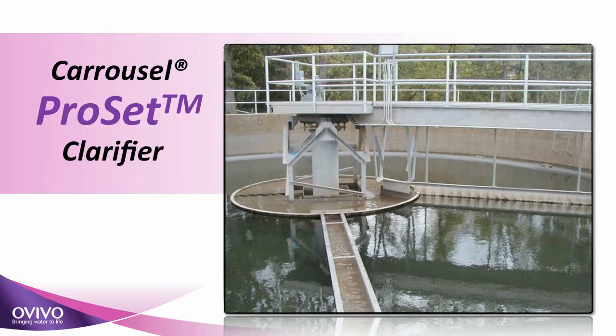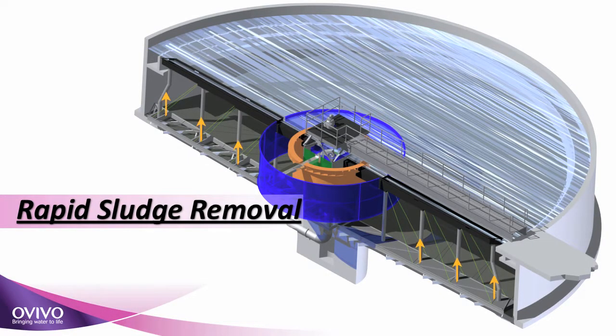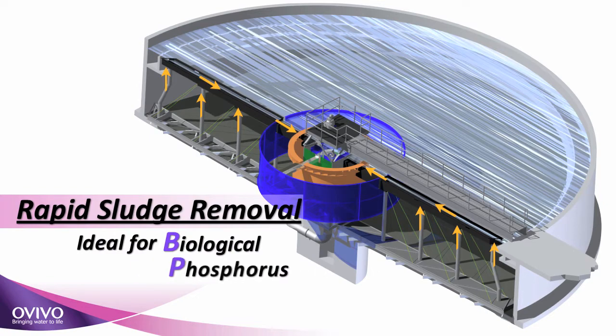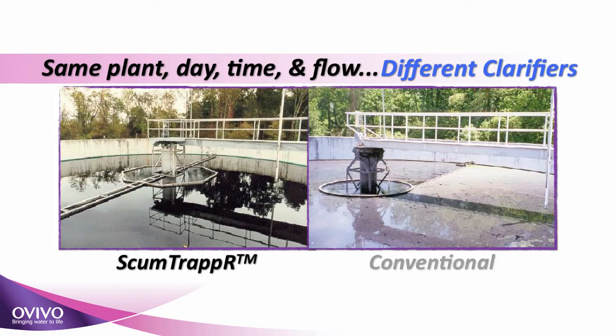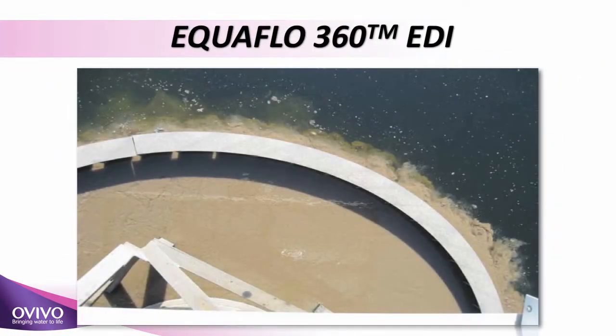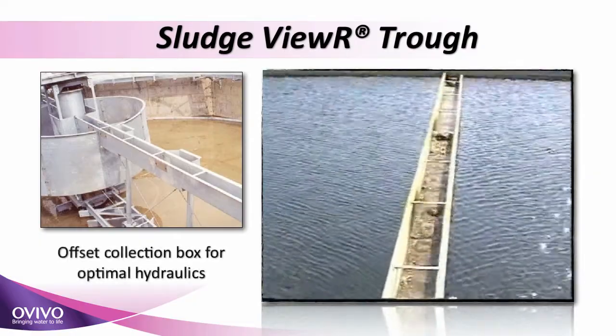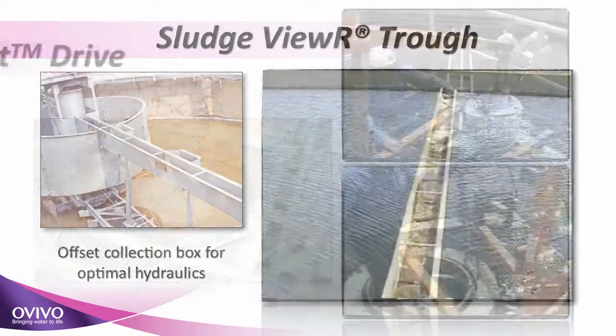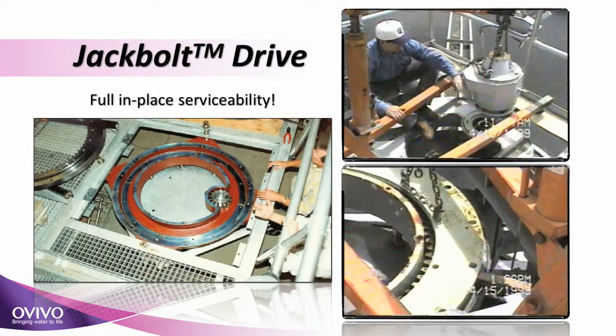We are also proud to offer the Carrousel ProSet Clarifier for enhanced biological nutrient removal. The Pro-Set Clarifier rapidly removes sludge, minimizing the sludge blanket residence time. Because long sludge blanket residence times cause effluent phosphorus numbers to increase, the Pro-Set is your best solution for biological phosphorus removal. Standard features include the Scum Trapper Feed Well for a clean clarifier surface, the Equaflo 360 EDI for improved flocculation and resultant settling, the Sludge Viewer which keeps the RAS in plain sight, and the jack bolt drive allowing full disassembly of the drive without removal.